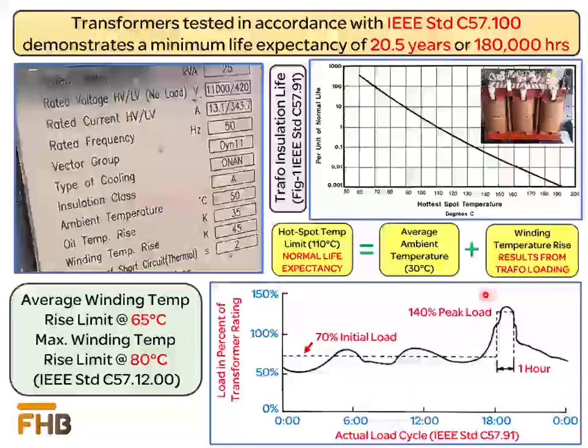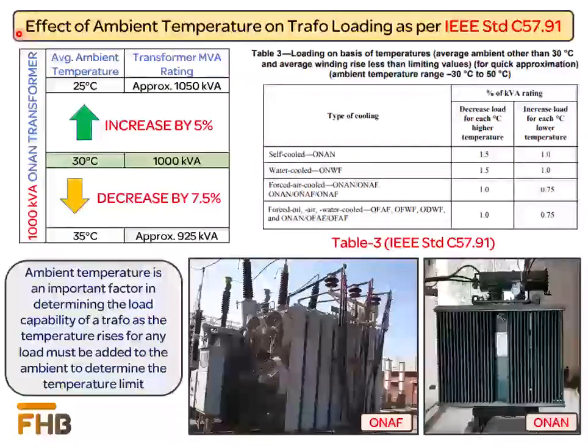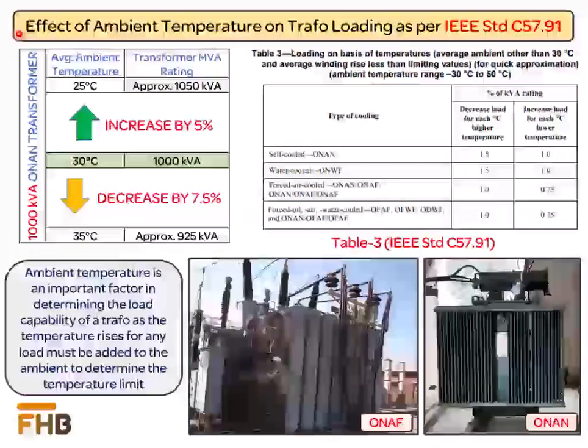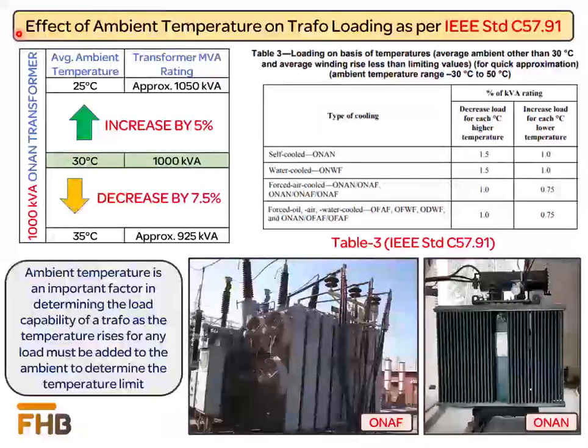Since the life of the transformer is dependent on thermal aging of the insulation, which is temperature dependent, transformer normal life expectancy loading is defined as continuous loading which results in a hot spot temperature under the limit of 110 degrees centigrade, assuming an average ambient temperature of 30 degrees centigrade. As we have already discussed, the hot spot temperature of the transformer is obtained by adding the ambient temperature and the transformer temperature rise due to the loading condition. Ambient temperature is the temperature in contact with the transformer radiators and heat exchangers.